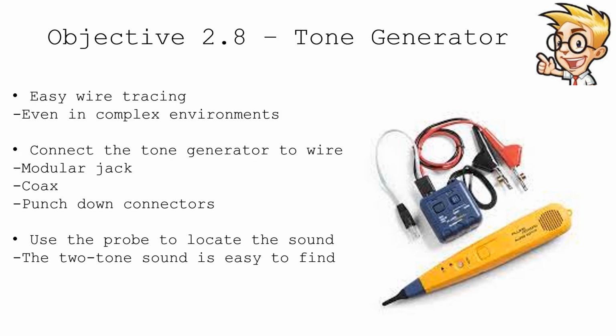This allows you to easily find where a cable might be, especially in an environment where hundreds or thousands of cables are being run across a data center. You would first connect the tone generator to one end of the wire. This could be done with a modular jack that's on the tone generator, or you might have alligator clips to put on a connection type of cable. You would then go to the other end where this cable is, and in a large bunch of cables, you would use this inductive probe to move from cable to cable and identify exactly which cable contains that particular tone.